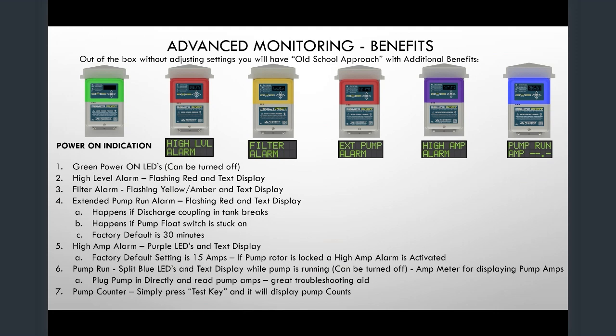So with this, you can go in and say, if you know your system's normally supposed to run for 2.5 minutes, you can go in there and set an extended run time. Let's say 4 minutes you establish, or even 3 minutes. That means if your pump ever runs longer than that, it shouldn't, there's something wrong with it. Maybe your discharge pipe broke and it's just recirculating in on itself, or your check valve broke, so it pumps it up, but then it comes back down and then it has to pump a little bit extra out next cycle. You would get your extended pump run alarm, and then you could come and check out your system and fix it before you had a major failure.